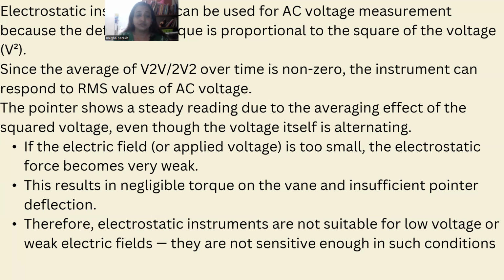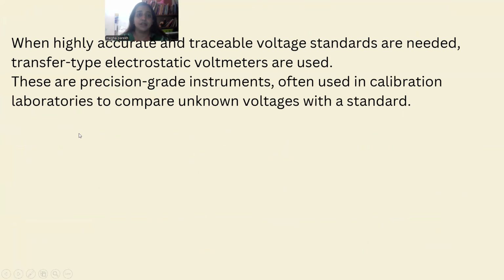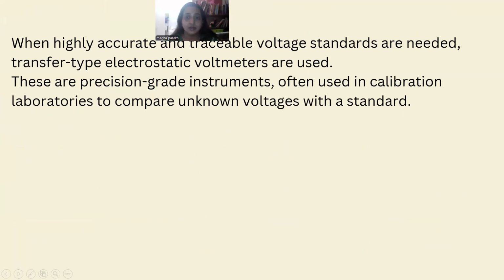Now let us understand that when the applied voltage is too small, the electrostatic force between the two plates becomes so weak that the generated deflection is negligible or null. So it's not suitable for low voltage applications. It is only used to measure high voltages. When highly accurate and traceable voltage standards are needed, transfer type electrostatic voltmeters are used. These are precision-grade instruments often used in calibration laboratories to compare unknown voltages with standards.